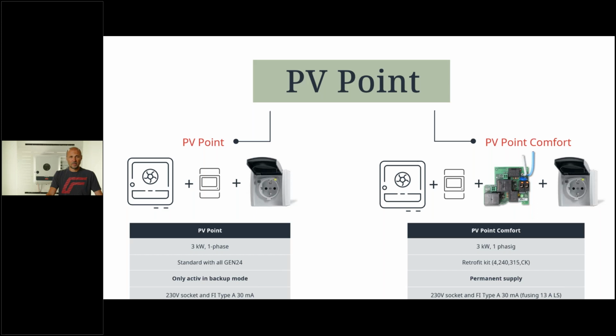So take care that you also have an RCD type A here, and probably fusing is also required. A 13 amp or 16 amp fuse is required. So if the fuse in the AC line is higher than 16 amps, you should also have an RCD here including fusing of 13 amps.